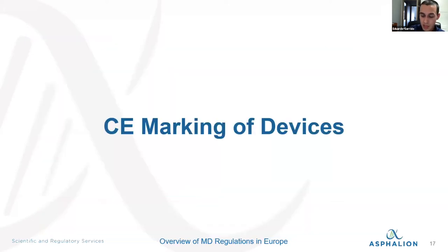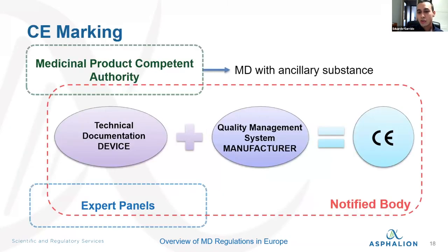So let's talk a bit in the last minutes about CE marking of devices. How do you CE mark your device? In order to CE mark your device, you need two basic things: first, technical documentation, and second, a QMS. It's mandatory for manufacturers in Europe to have a quality management system based on ISO 13485.